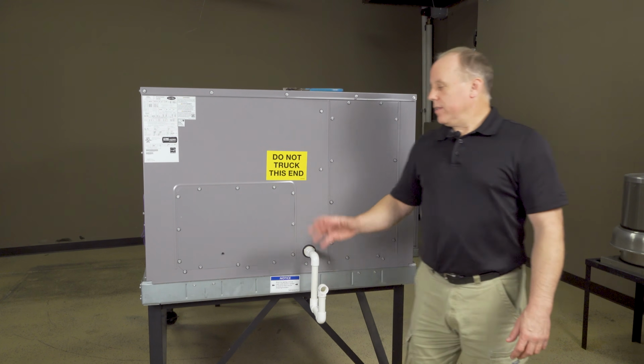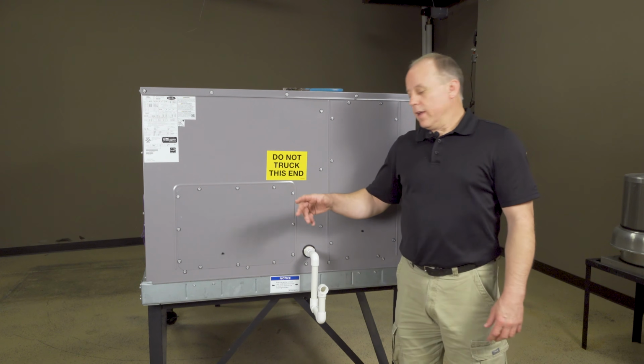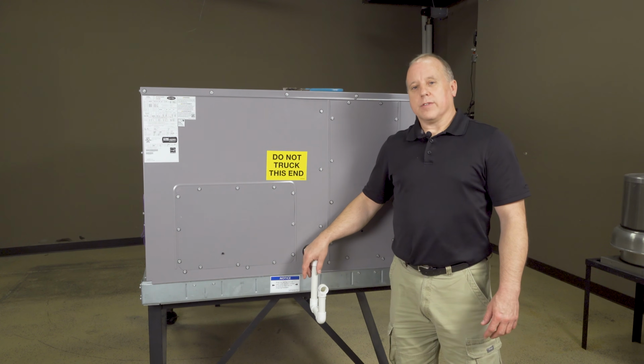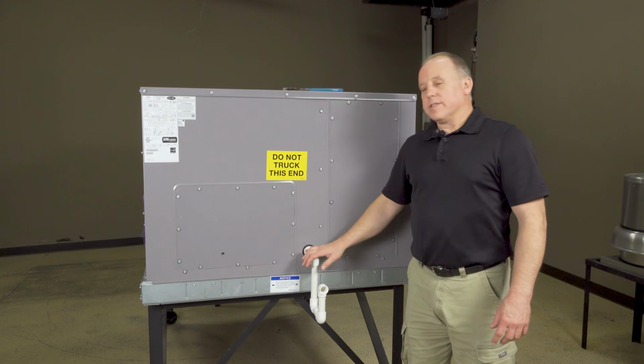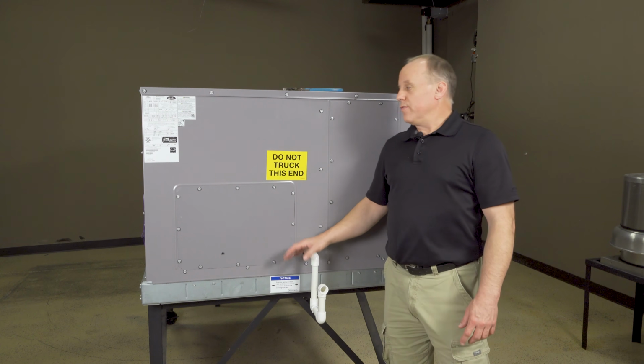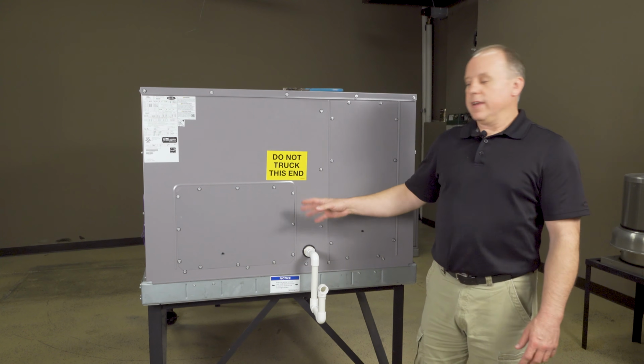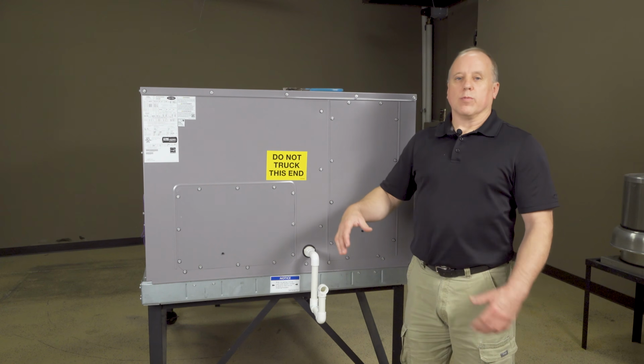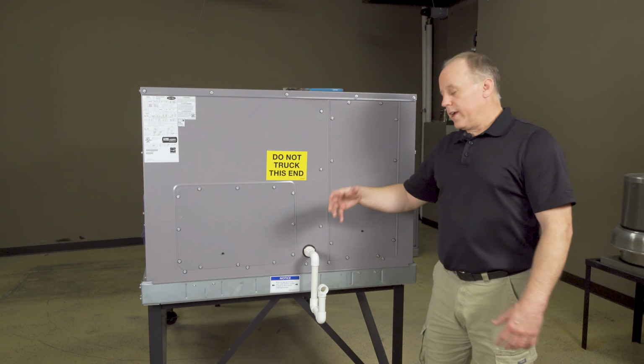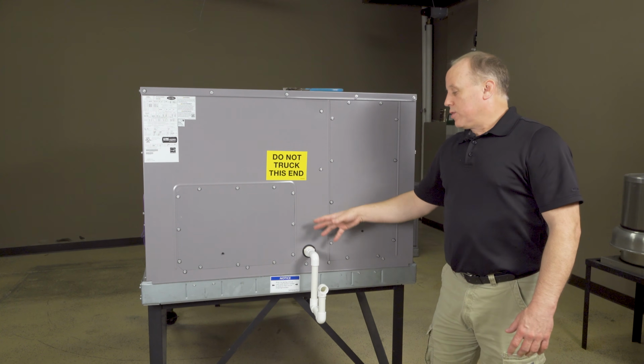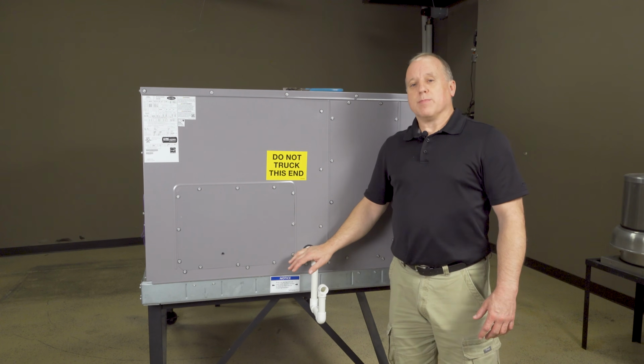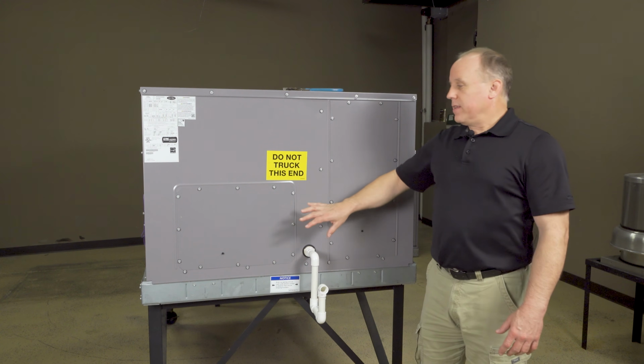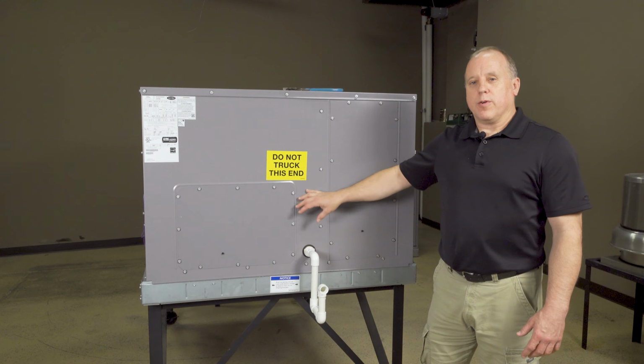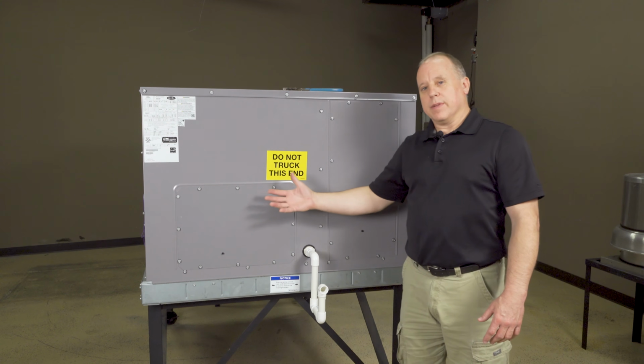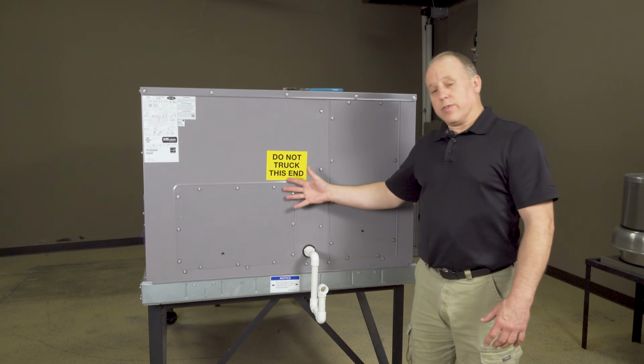Okay, when doing the maintenance, along with the coils and cleaning, we also want to make sure our condensate trap gets cleaned. This condensate trap is going to run the condensation from the evaporator coil on our AC unit onto the roof, onto the ground, wherever it's draining to. We want to make sure this is clear, because if this gets backed up, we could have backup into the pan at the evaporator coil, which will then back up into the building that we're sitting on.